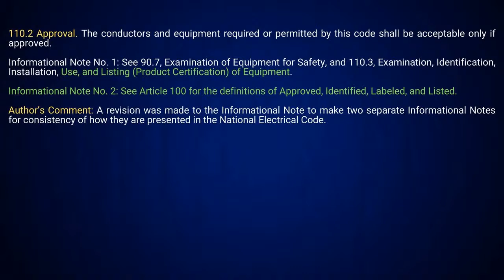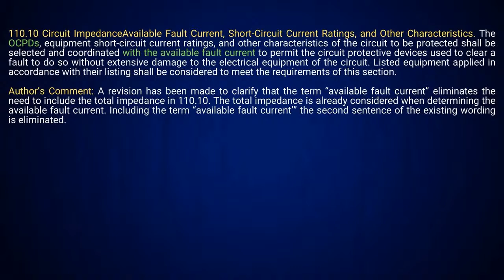All right. Then they made another revision. This is to clarify when you're dealing with the term available fault current here. And what this will help do is eliminate the need for you to also include the total impedance, because when you actually look at total impedance, it's already considered when you're determining what the available fault current is anyway. So they just fixed some wording there to help clarify that, and that helps tie in when we're looking at 110.24 A and B.